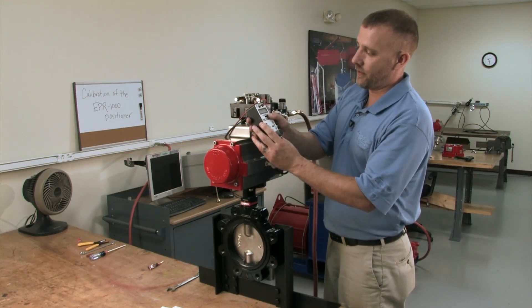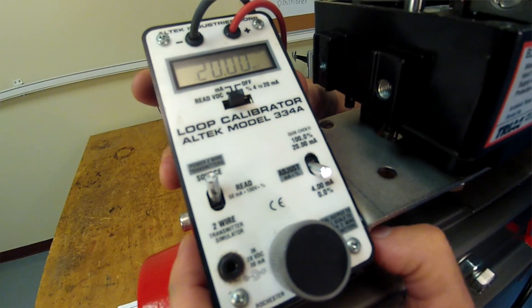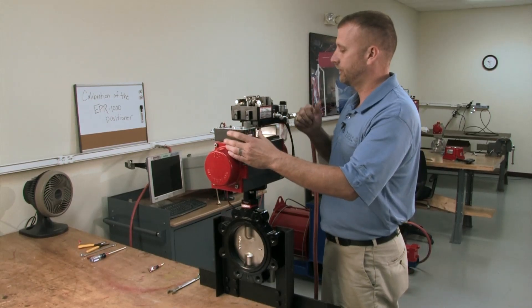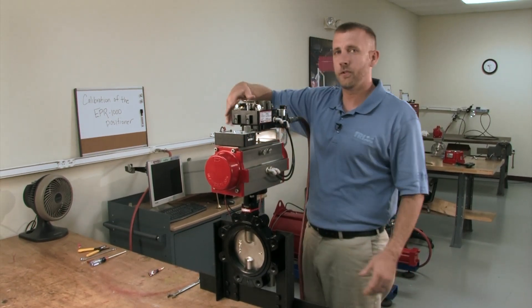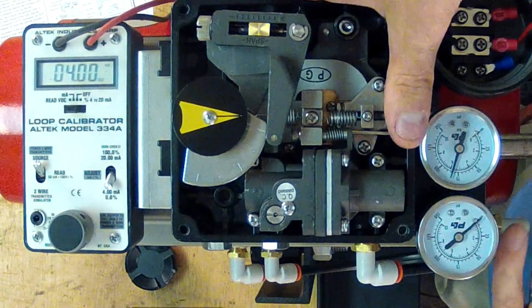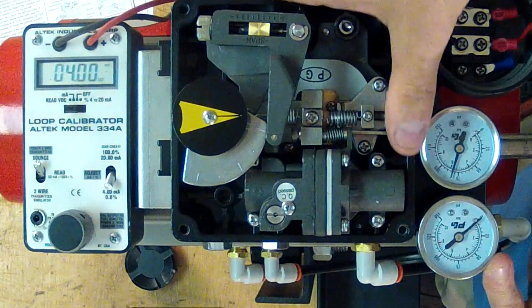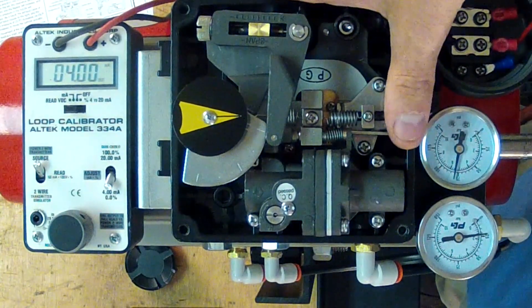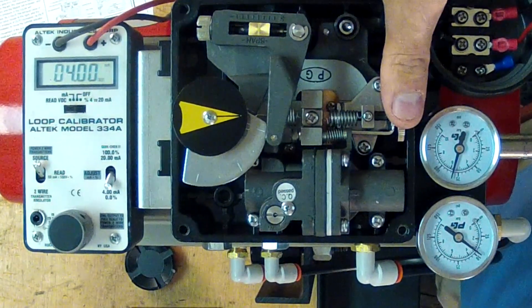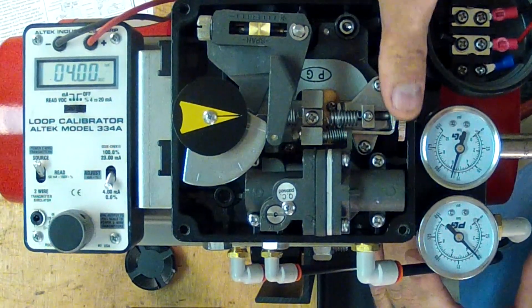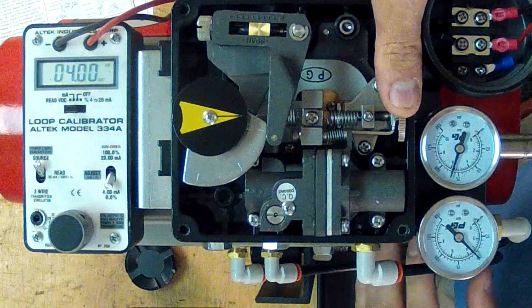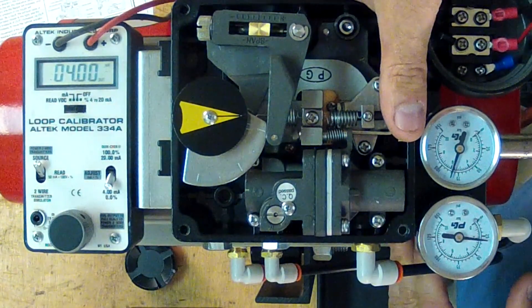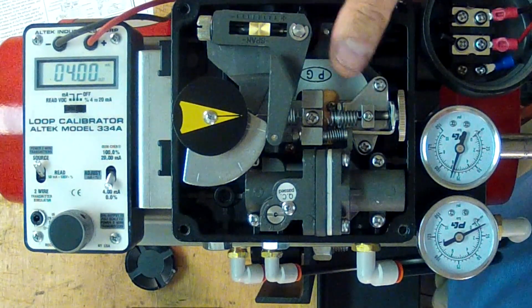Now, turn your calibrator on. I'm going to start at our 4 milliamp position. And what you do is you adjust your thumb screw clockwise until the gauge begins to climb. And once you notice it's climbed, you back it off counterclockwise until it falls nice and slow down to the zero position.